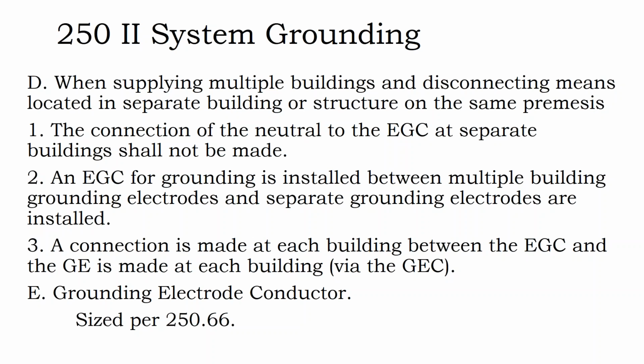A connection is made at each building between the equipment ground conductor and the grounding electrode. So I guess these are different ways that you can ground. You're still connecting your equipment ground conductors between the multiple buildings, and you may be installing grounding electrodes at multiple buildings so that your ground is at a zero reference point.